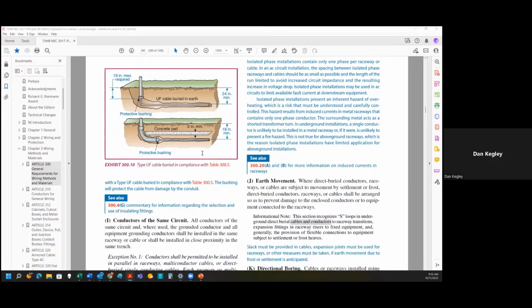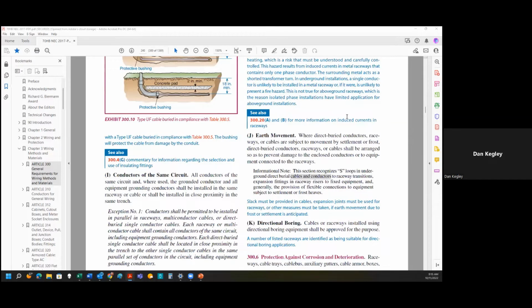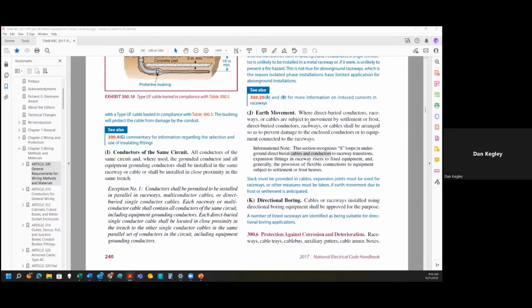Then it goes into I, conductors, the same circuits. Then J is where we talked about that earth movement. This is where direct buried conductors, raceways, or cables are subject to movement by settlement or frost. Then the direct buried conductors, raceways, or cables shall be arranged so as to prevent damage to the enclosed conductors or to equipment connected to the raceway. Again, that's where we have like a junction box. It's not going to move, but you'll have the ground pushing up on that raceway, trying to push it up on that box that's not moving, causing damage. Or I've actually seen it pull that conduit right out of the box and then expose the wires.